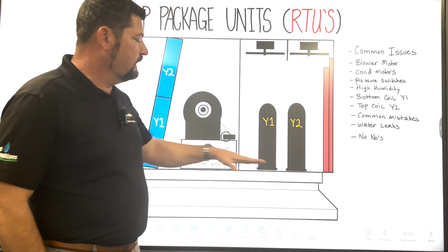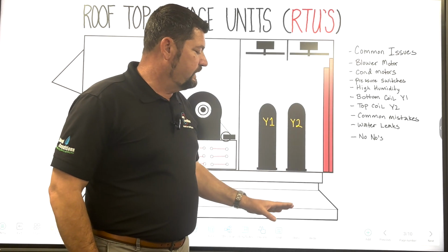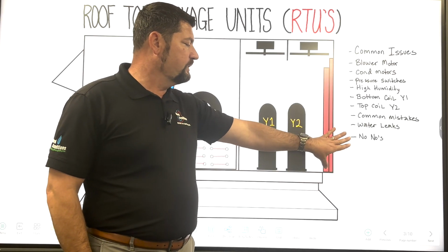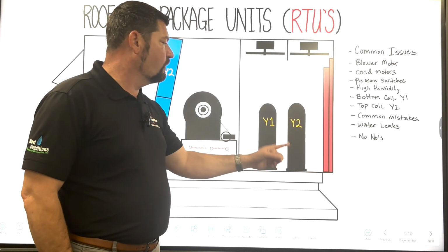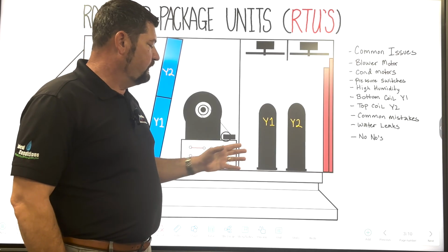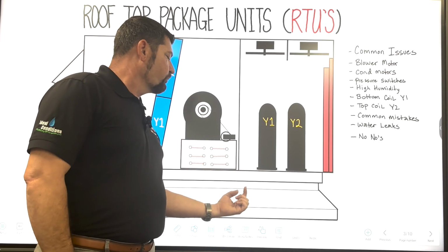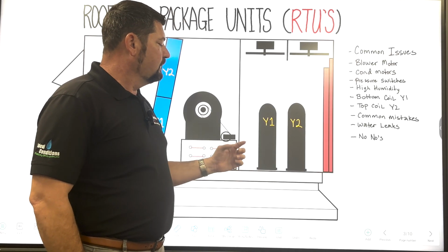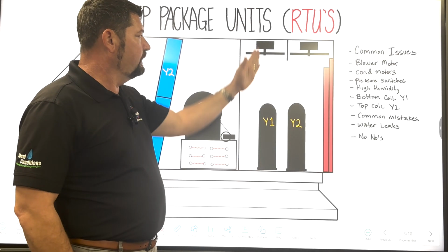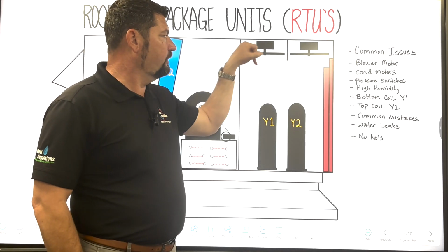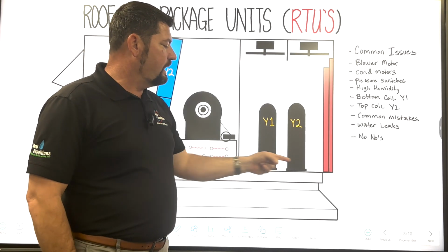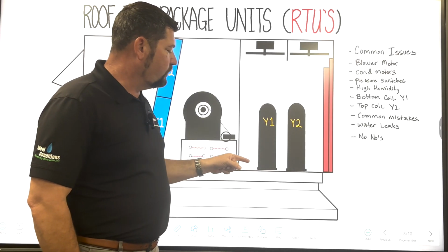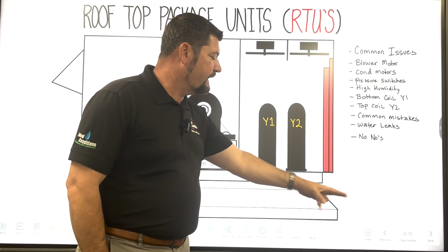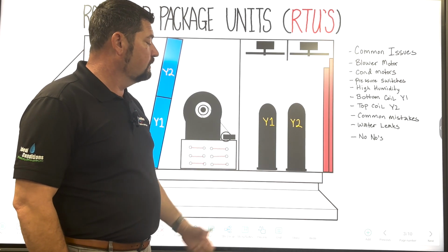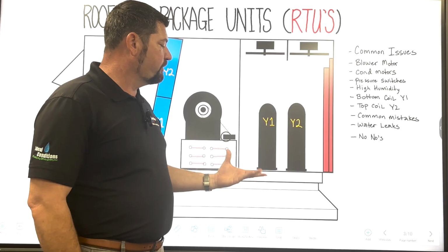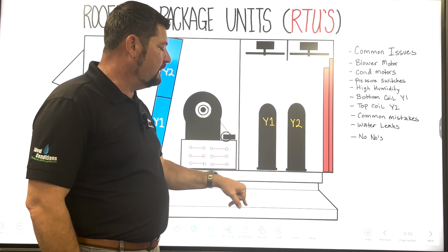There's these units that get installed. The electrical should be coming out of the roof deck, going to a disconnect box, and then out of that, an electrical whip should be going into the unit. And then we should be feeding our electrical panels, not coming through the bottom of the package unit and then siliconing them, because water comes into the unit naturally from the tops of the condenser section, water can pool up in here, and if the channels inside these units that allow that water to drain out are clogged with anything, just debris, by not having proper maintenance, that water just kind of sits in there, accumulates, and that could even leak down.